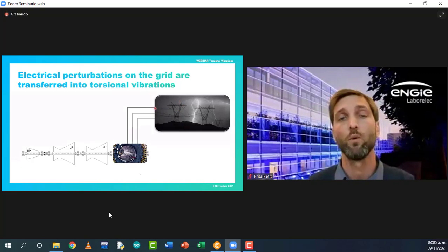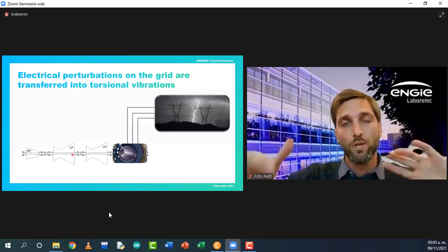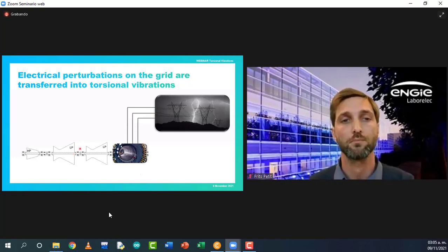If this would hit one of the transmission lines, it would create a perturbation on the electrical side, which is then transferred through the generator on your turbo generator shaft line, which will respond in terms of torsional vibrations, which is a twisting motion of the shaft line. Now, normally a lightning strike and other typically occurring transient events like short circuits on the grid, they do not threaten the structural integrity of the shaft line. However, there are other interaction mechanisms that do threaten the structural integrity, and the probability of those occurring is increasing due to the ongoing grid transition.